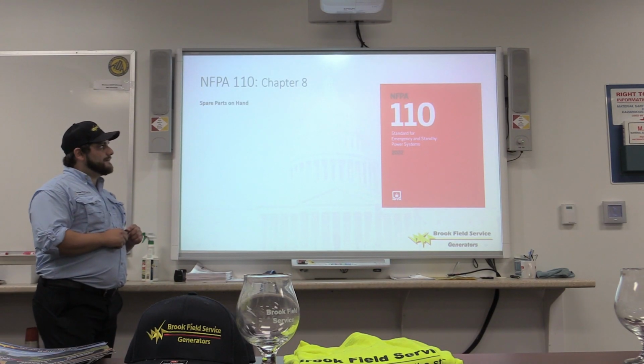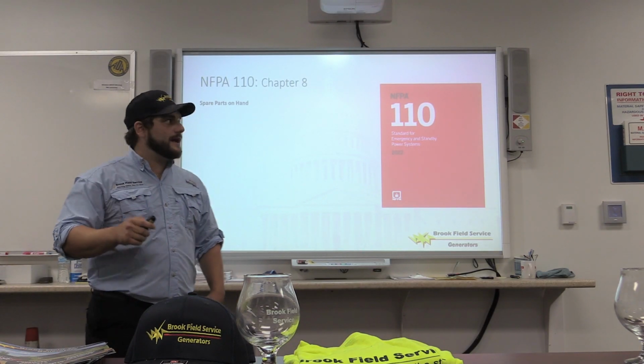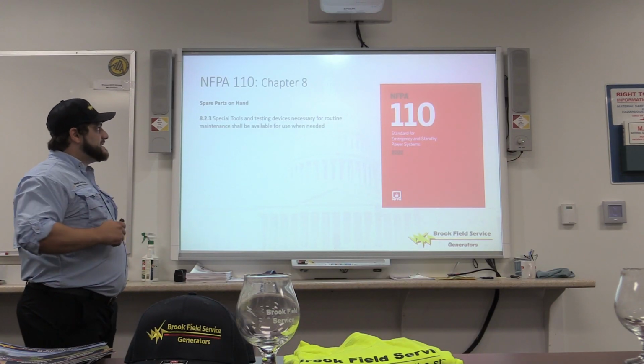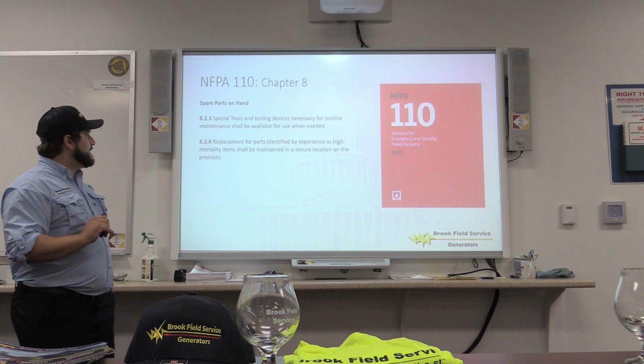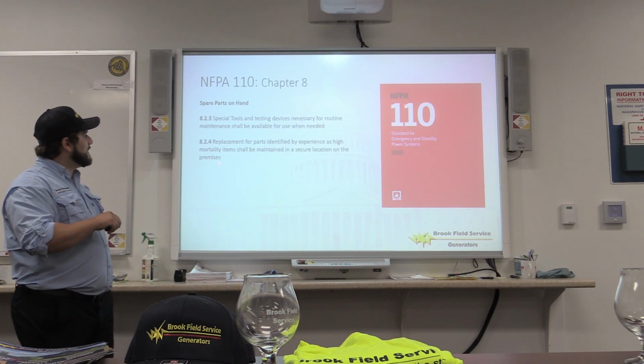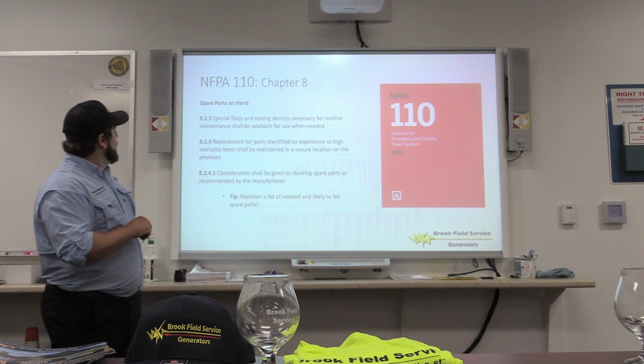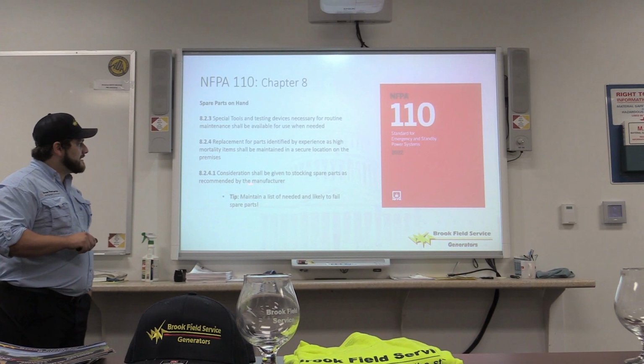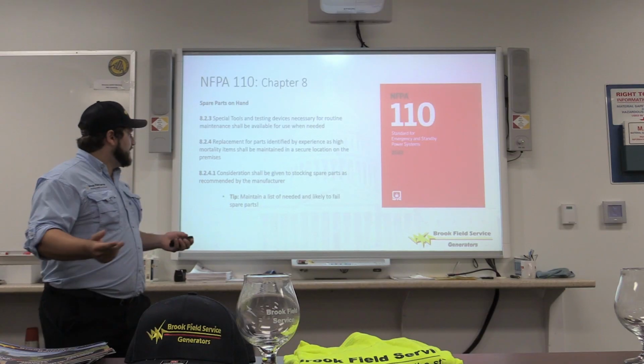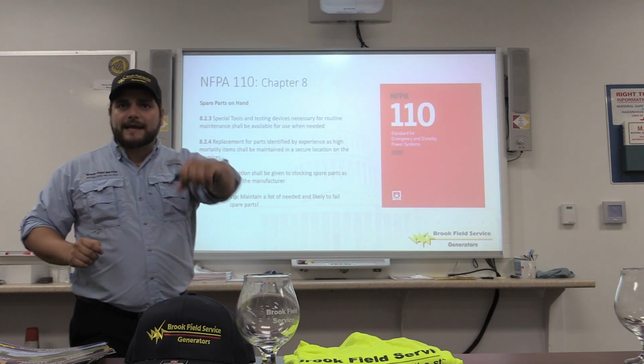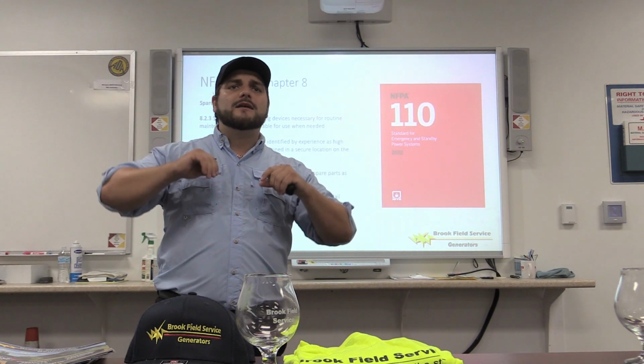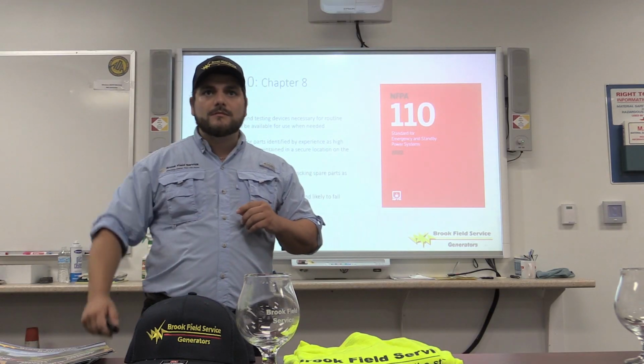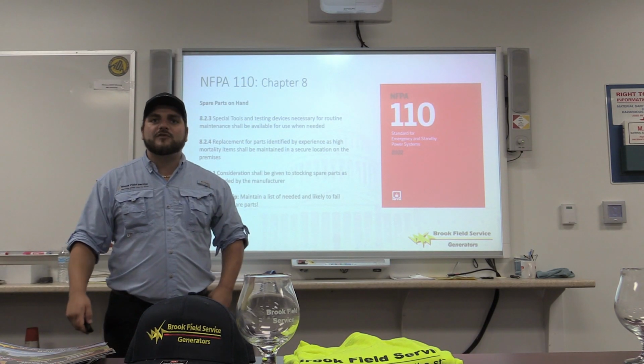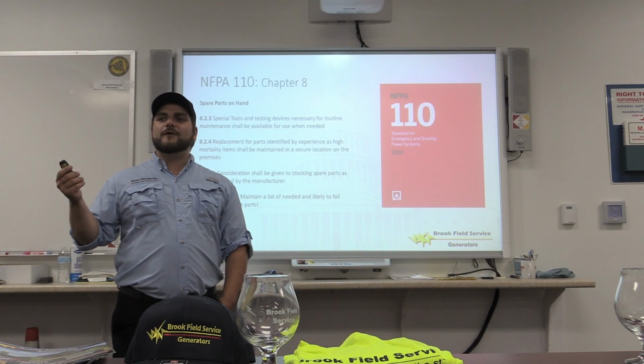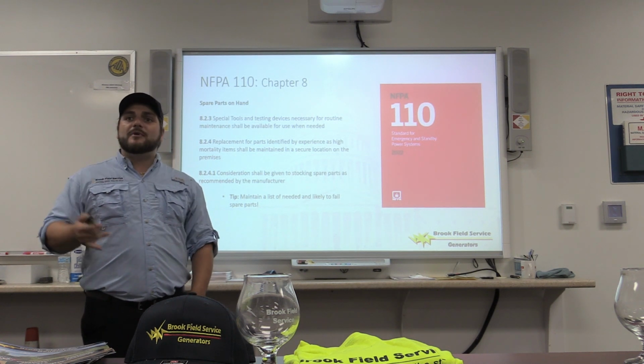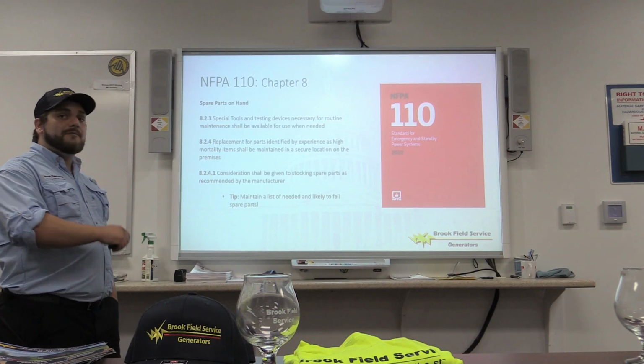The first thing I think is very important to emphasize, Josh has seen it all too many times, and I know Jim really wanted me to emphasize this today, is spare parts on hand. Special tools and testing devices necessary for routine maintenance will be available for use when needed. Replacement parts identified by experience as high mortality items will be maintained in a secure location. Consideration will be given to stocking spare parts as recommended by the manufacturer. A little tip: just maintain a list of what's needed and likely to fail. Josh, just off the top of your head, can you name two high mortality items? Block heaters and drive belts, fan belts, stuff like that. Perfect. I'm sure you'll get into more of that, but those are two things that just get overlooked, or sometimes the funding might not be there. If you have anything extra to put towards your spare parts, it might help you in a disaster.